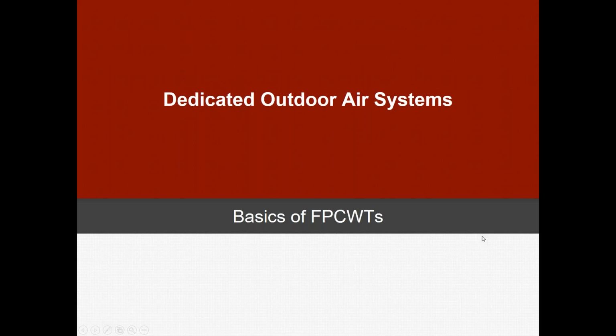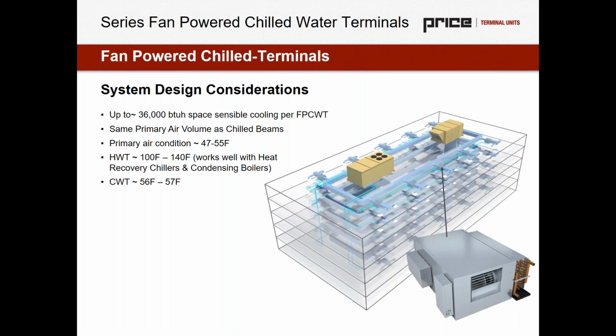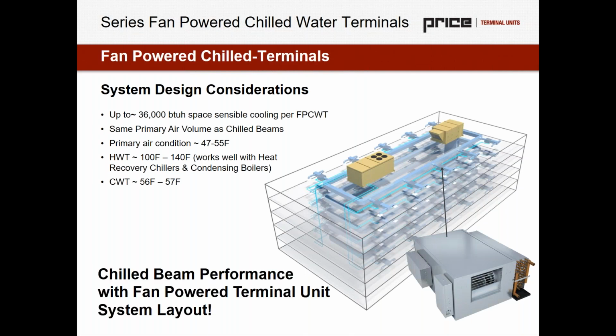So now I just want to take a quick look at the basics of our fan powered chilled water terminals, which is in many ways more my bread and butter. It's the product that I work with on a daily basis and the one that I tend to have the highest interest in. And when we look at system design considerations, really the nature of the beast here is that it's chilled beam performance with a fan powered terminal unit system layout. So we're looking at some differences as far as how densely the equipment is supplied. When I say densely supplied, I'm talking about the energy density available at the equipment.